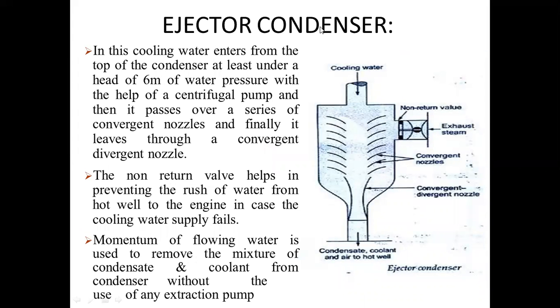If we are talking about the ejector condenser, then you can see the ejector condenser here. Cooling water enters from the top of the condenser under a head of at least 6 meter of water pressure with the help of a centrifugal pump, and then it passes over a series of convergent nozzles. You can see this is a series of convergent nozzles. Exhaust steam enters from here, right? There is a non-return valve, so water and steam cannot go outside, they can only enter into the nozzle, into the system. The non-return valve helps in preventing the rush of water from the hot well to the engine in case of cooling water supply failure.